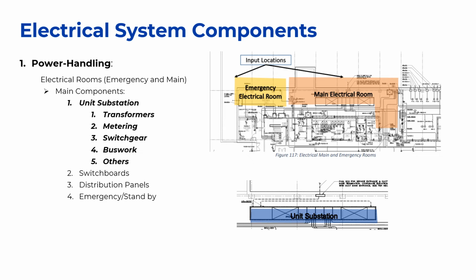The most important component to deal with is the unit substation, an assembly comprising a primary voltage switch and fuse or circuit breaker, a step-down transformer, metering equipment, controls, buswork, and secondary low-voltage switchgear. Its main function is to accept an incoming high-voltage power supply, transform it to a lower voltage usable in the facility, and distribute the low-voltage power through associated low-voltage switchgear.